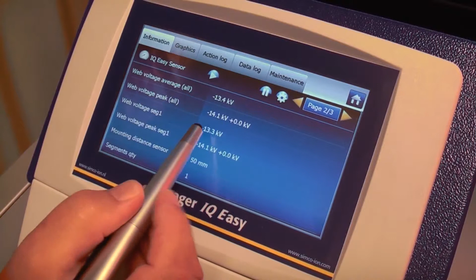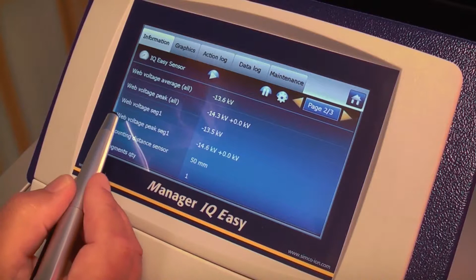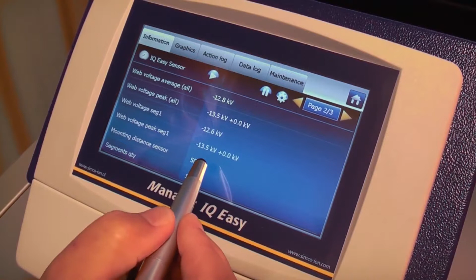you both values. It will show you the web voltage, the actual voltage of the measuring segment 1, which is, you can see, fluctuating between 12 kilovolts and 13.5 kilovolts. It will show you the peak voltage it has measured in this period. What is also important, the sensor needs to be positioned at a certain distance to be accurate for the reading. So at installation, you will have to tell the IQ Manager the right distance you have mounted the sensor.